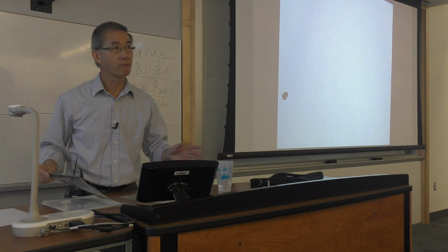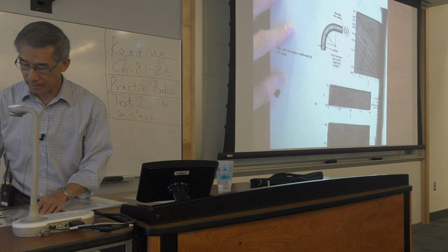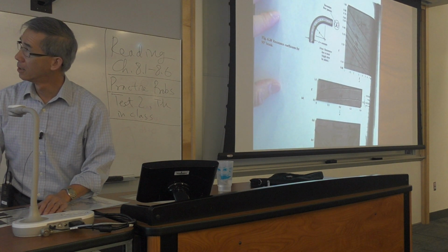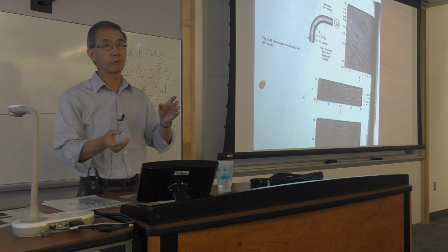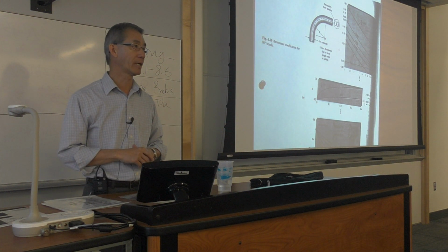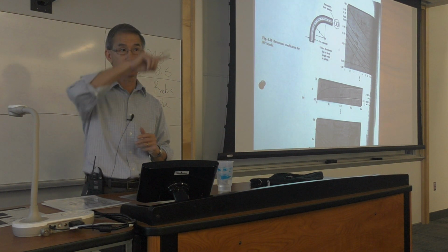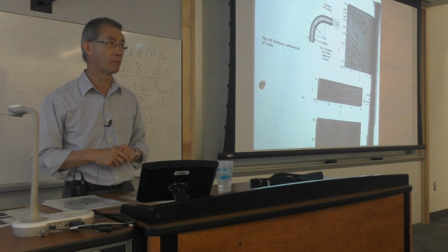So that's the valve, and then there are turns. Someone asked the question, when I have a 90 degree bend, do I need to know the radius of the turn versus the diameter of the pipe? Absolutely, this is how you attack that. An absolutely sharp turn is the worst. Just a sharp 90 degree. A little bit of radius helps a lot.